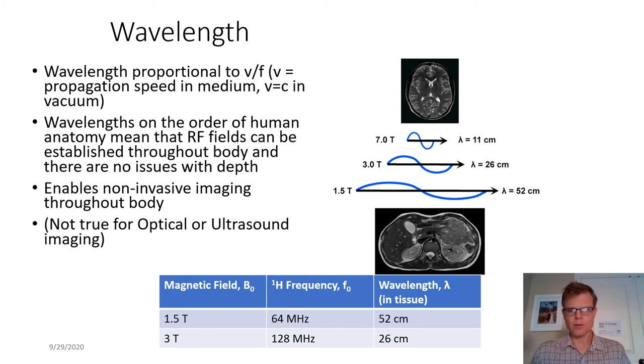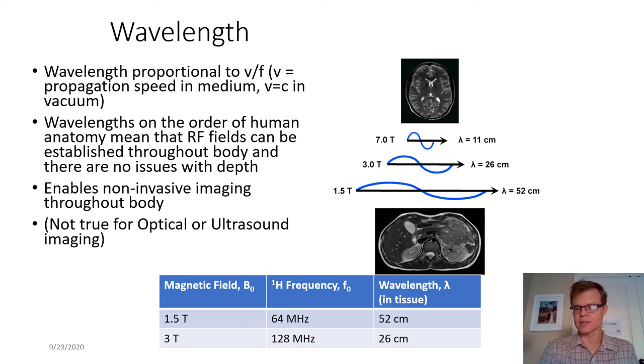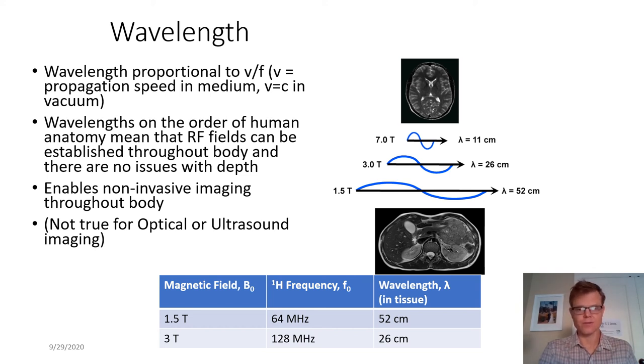Another consideration is that electromagnetic waves have a characteristic wavelength associated with them. It's proportional to the propagation speed — C, the speed of light in vacuum — divided by the frequency. The frequencies we're dealing with in MRI, a couple listed here for typical systems, are 64 and 128 megahertz. This drawing illustrates the wavelength of electromagnetic waves at this frequency. Compared to typical human body sizes, these wavelengths are about as big as the body, or a little less.